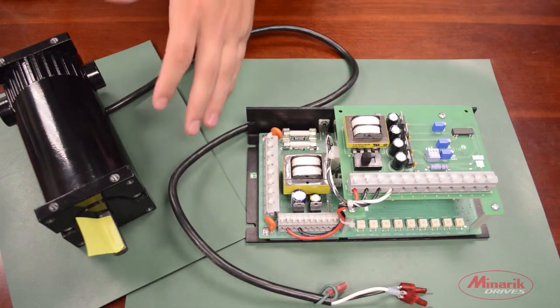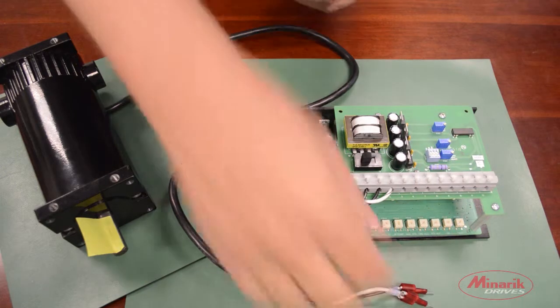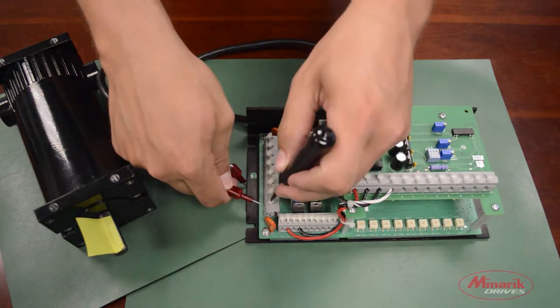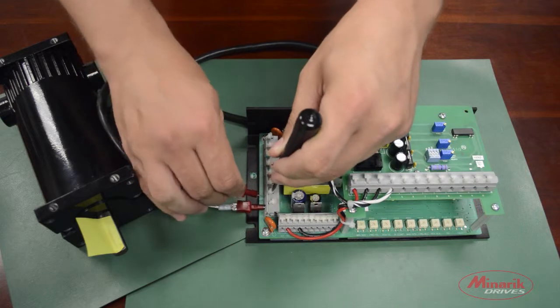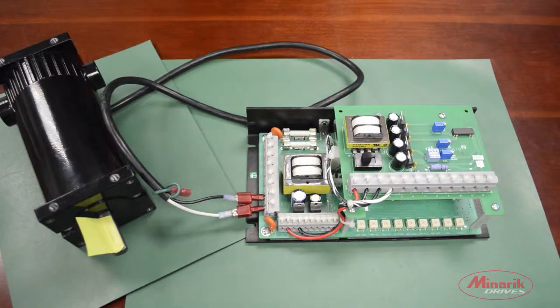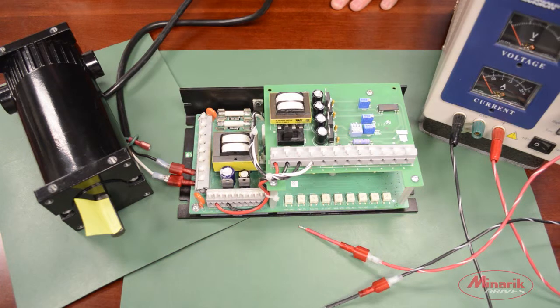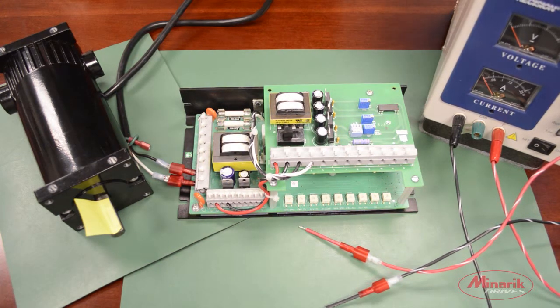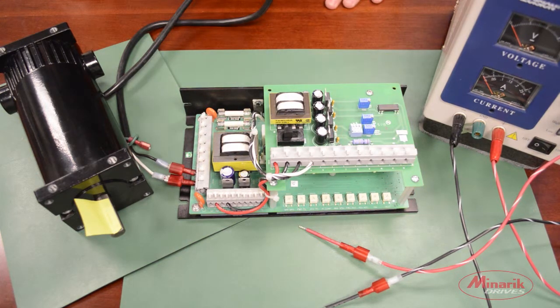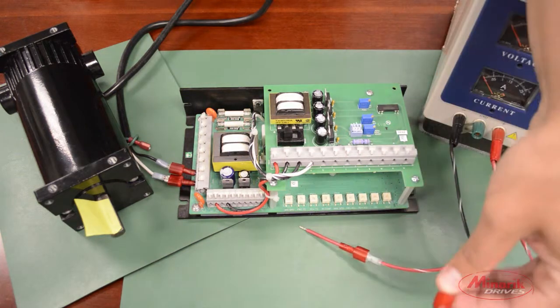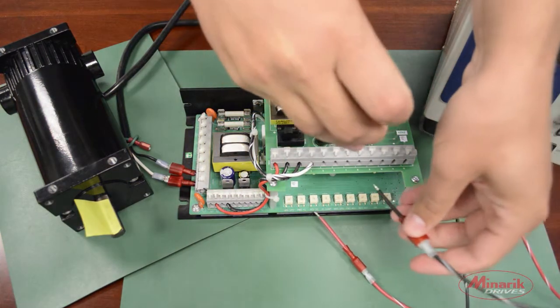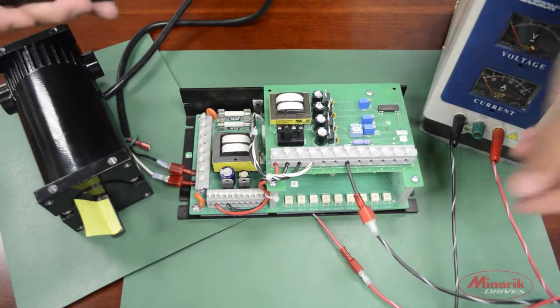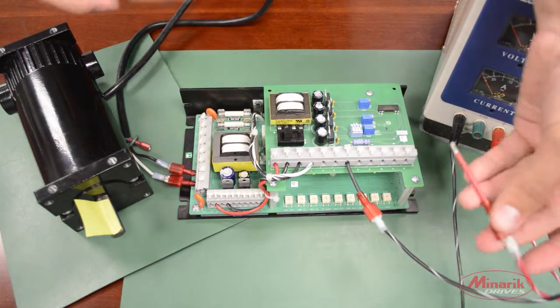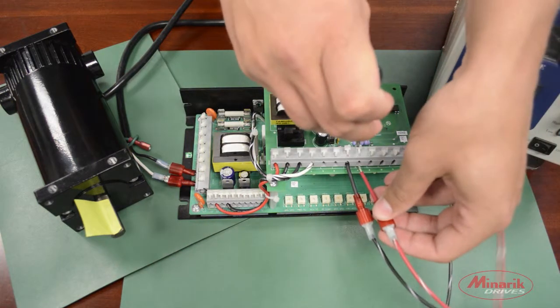Next, we're going to connect the armature leads from the motor to the drive. These will go in A1 and A2. Now we'll be connecting our input signal leads to the isolation card. We'll be using a power supply to simulate our voltage input signal, and we'll be using a 0 to 10 volt range. Because we're using a 0 to 10 volt range, we'll connect our common lead of our source to the common terminal, or pin 7, of the isolation card, and the positive lead of our input signal to input 1, or pin 8, of the isolation card.